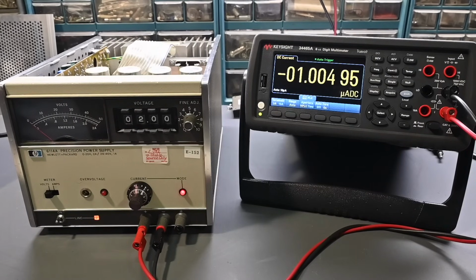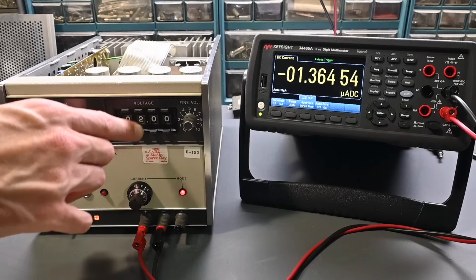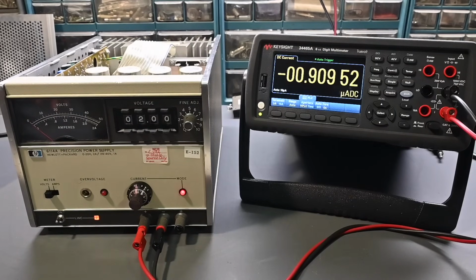So what you're supposed to do is turn on the power supply and set it for 2 volts. So I've done that. And then on the back panel, you're supposed to turn off the current control by connecting a jumper from position A6 to the positive output. So I have that jumper in place. And this is where I'm doing things a little bit different from what's described, but the end result will be the same. So you're supposed to connect a 0.1 ohm plus minus 0.1% resistor across the output terminal, so a very low value precision resistor. Although a little bit later on it says to use a 1 ohm resistor, and I think it's a typo, I think the decimal point fell off.